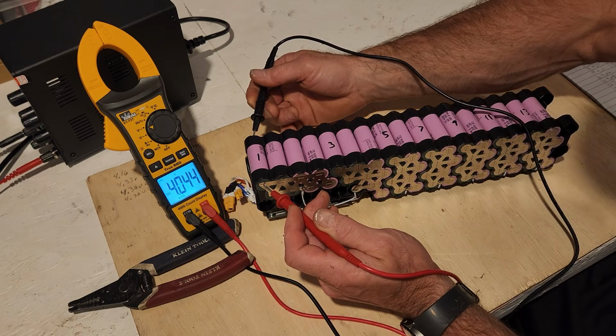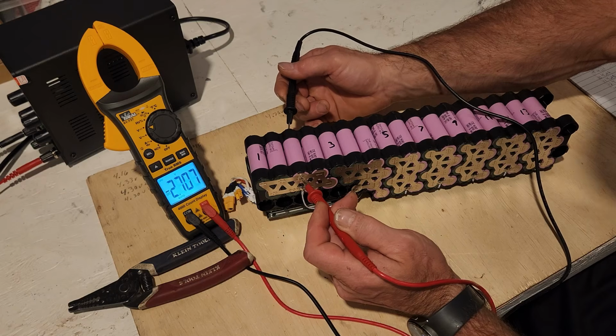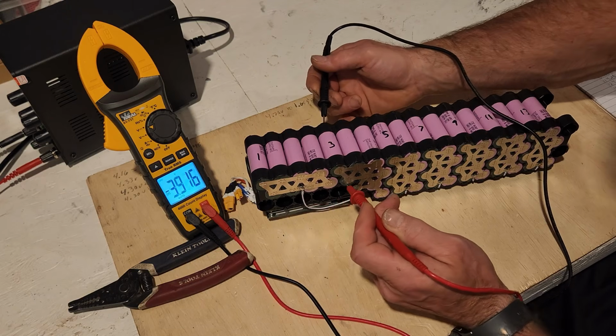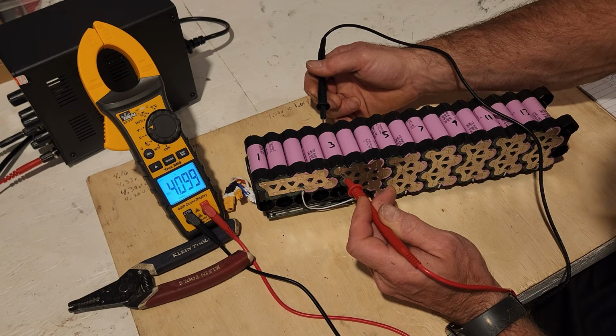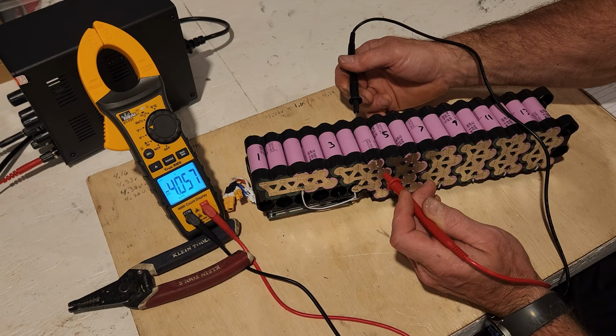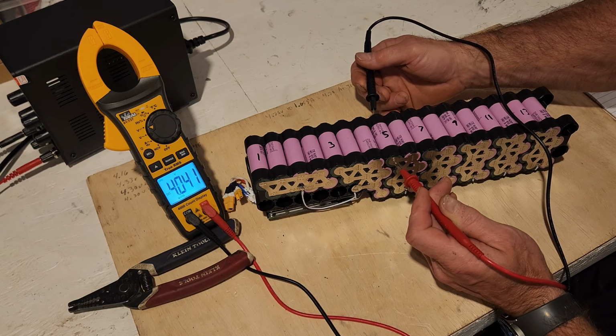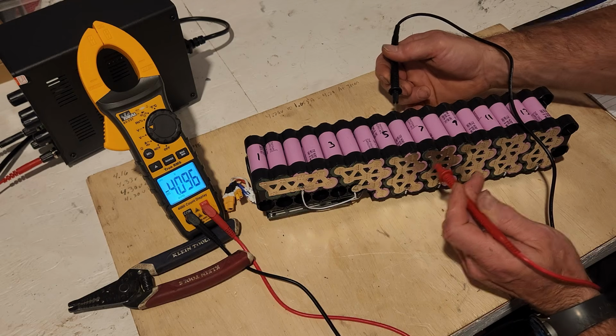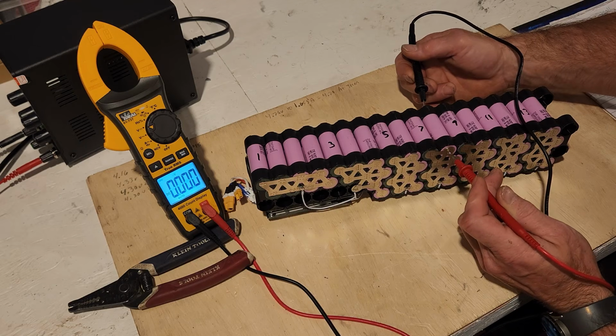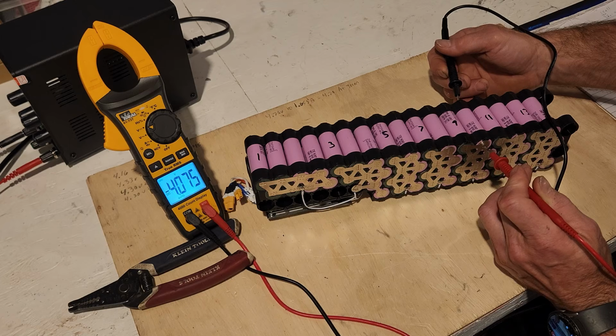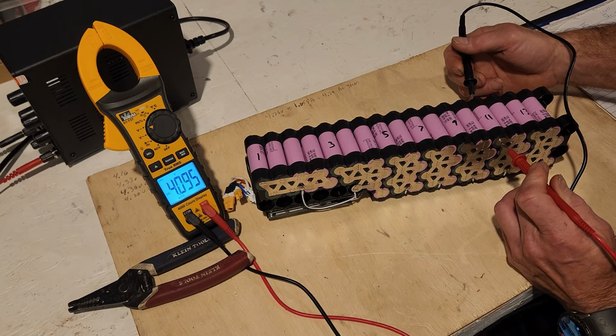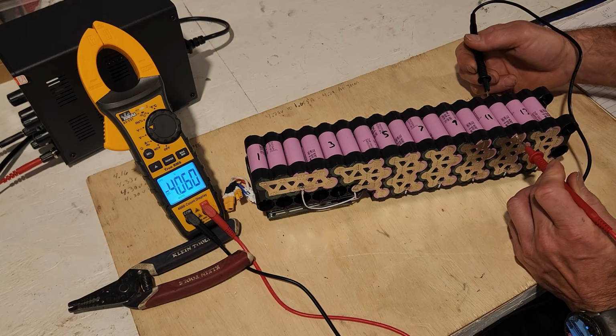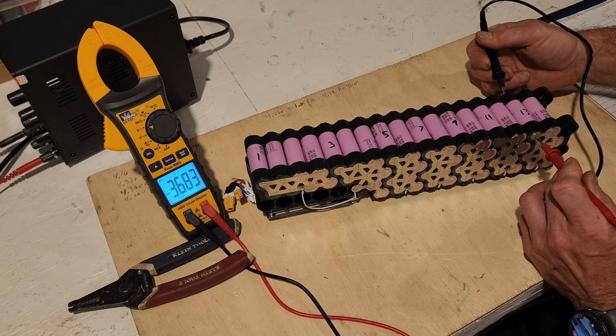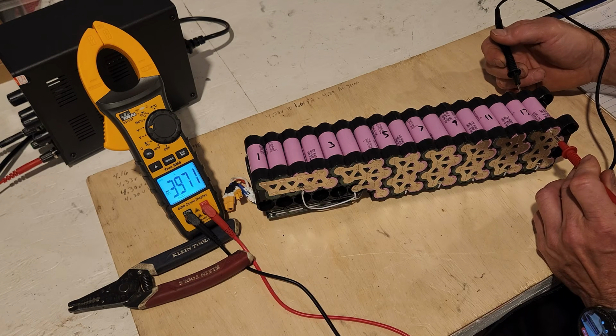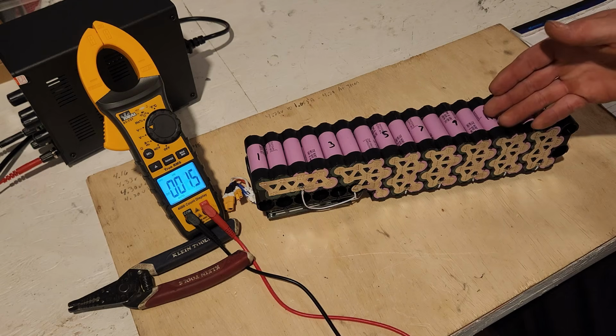So group number 1, 4.04. Group 2, 4.12. 4.09. 4.05. 4.04, 4.09, 4.06, so they're pretty close. You got a 3.94, 4.11, 4.07, 4.09, 4.06, and we got a 3.68, 3.97. So you can see like 3.68.